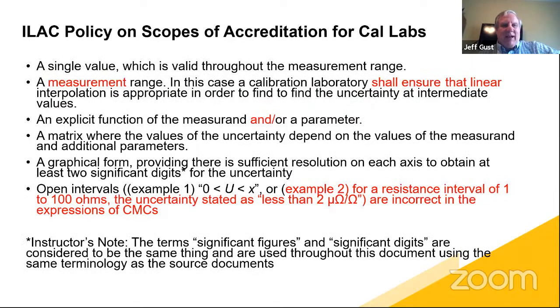So you could express it lots of different ways. If you said that I'm going to have a measurement range of 0 to 1,000 volts, well, you can put in a single value. However, that uncertainty has to be valid throughout the entire measurement range. So it would probably be the best of the worst along that range, because you could measure 2 microvolts per volt at 1 volt, or 2 parts in 10 to the 6 at 1 volt, but at 100 volts, your uncertainty is 50 parts in 10 to the 6. Your single value can't be 2 parts in 10 to the 6 because that's not valid at 100 volts. So you might need to break down into smaller measurement ranges.